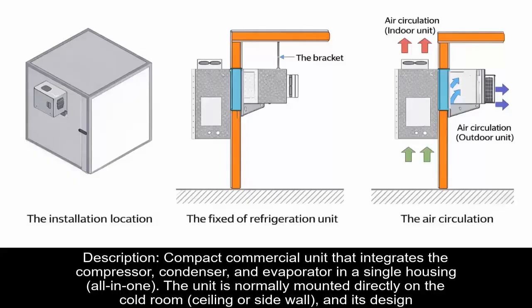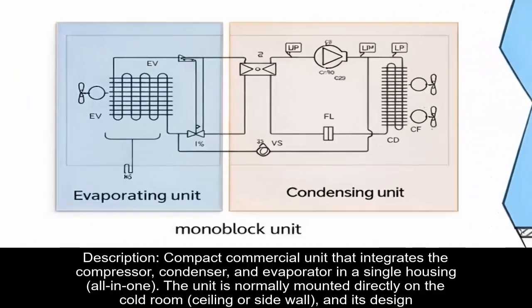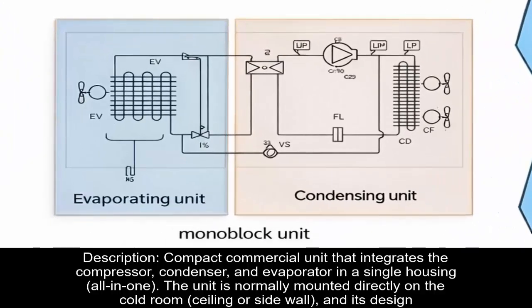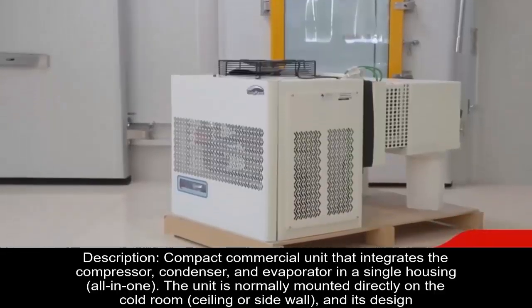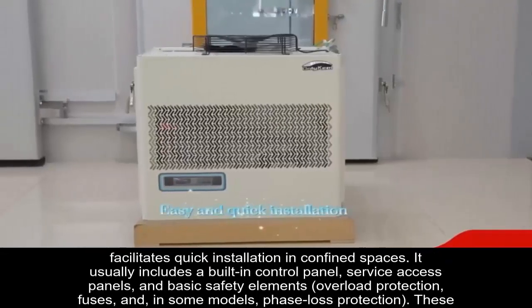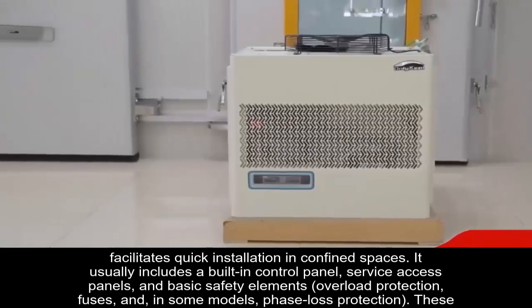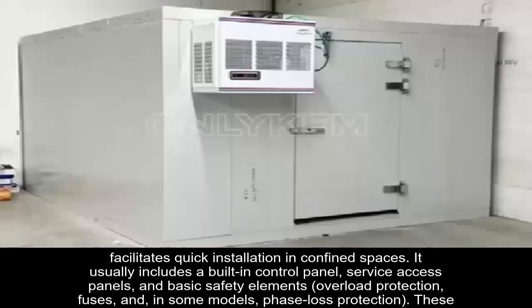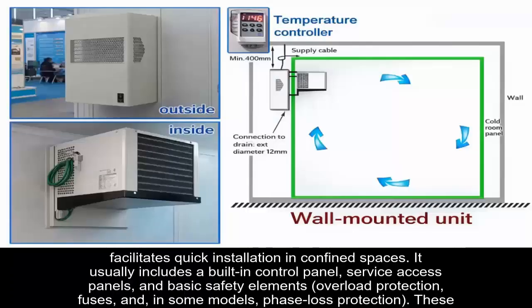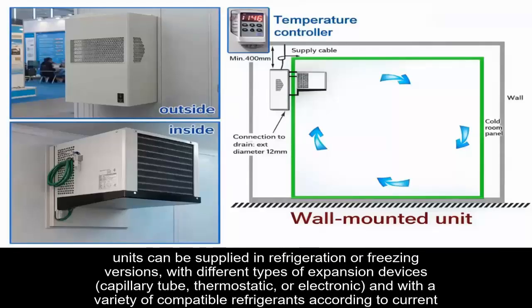Description: compact commercial unit that integrates the compressor, condenser, and evaporator in a single housing, all in one. The unit is normally mounted directly on the cold room, ceiling, or sidewall, and its design facilitates quick installation in confined spaces. It usually includes a built-in control panel, service access panels, and basic safety elements: overload protection, fuses, and in some models, phase loss protection.